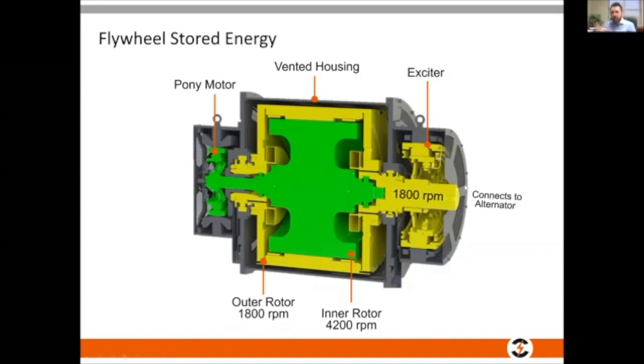Now, if the alternator is always spinning at 1800 RPM, then where we connect to it is also spinning at 1800 RPM. It has to. So anything that's yellow in this photo is spinning at 1800 RPM because it's connected to the synchronous motor. And when the mains fails, what we've said is we need to transfer the energy from the flywheel to make sure that the 1800 RPM that's spinning never slows down.